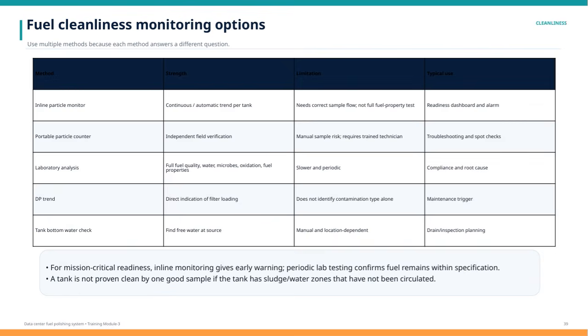Laboratory analysis offers a comprehensive assessment of fuel quality, including water content, microbes, oxidation, and other properties. While it's more thorough and used for compliance and root cause analysis, it's slower and done periodically rather than continuously. Differential pressure trend monitoring directly indicates filter loading, helping trigger maintenance, but it doesn't identify the type of contamination on its own. Lastly, tank bottom water checks help find free water right at the source. This method is manual and depends on location, but is essential for planning drain and inspection activities.